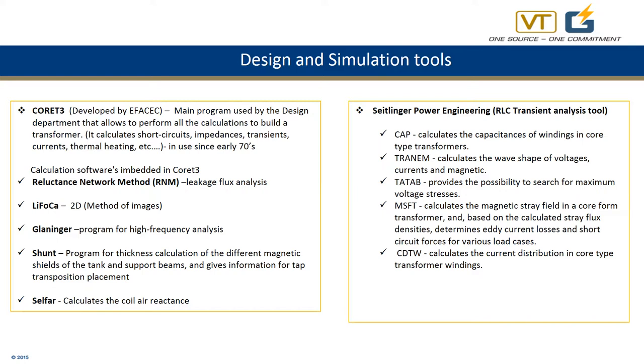Let me also talk about a very powerful simulation tool, Seitlinger. This is also a homegrown tool, from EFACEC, developed to check the limits of the design in terms of voltage stresses. There are subprograms within Seitlinger too. MSFT calculates magnetic stray fields in core form transformers and, based on stray flux densities, calculates eddy current losses and short circuit forces for various load cases. Another subprogram, TATAB, searches for voltage stresses in different parts of the transformer.